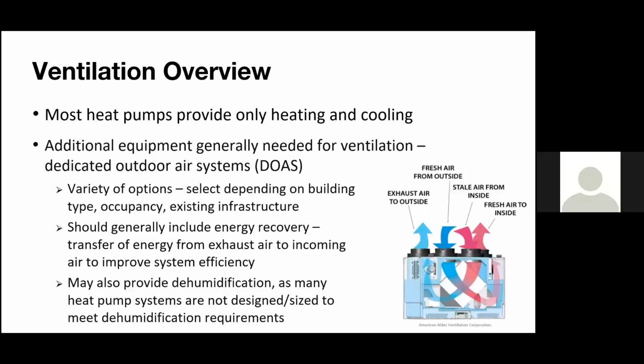But also what you can do is use a DOAS system. You can have a rooftop unit that has a wheel, to transfer energy there. So if we're at 0 degrees outside, that wheel brings it up to 30, 40 degrees. And then you have some kind of mechanical system that heats and cools the space. So if we're in heating mode, we could have natural gas burning, or an electric coil of some sort, or you can even connect heat pump systems to get your heating capacity that way, to bring that 40 degrees off the wheel up to room neutral air at 70, 75 degrees.